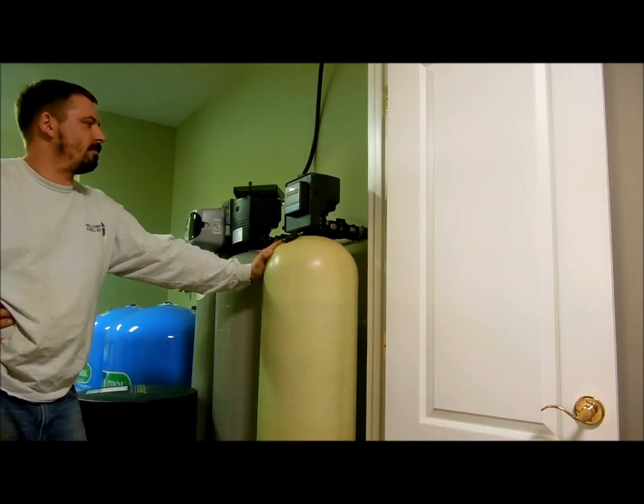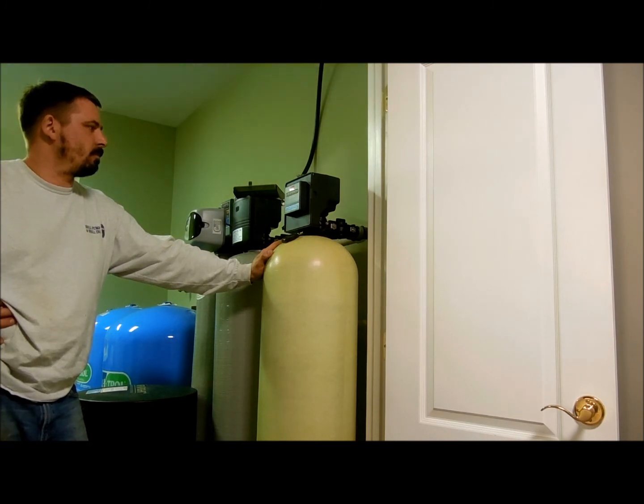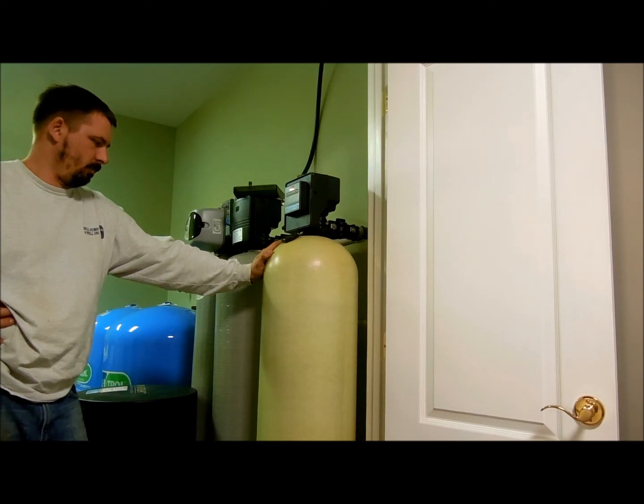Once you are done rinsing, you should make sure the clock is set for the correct time of day. Your filter should already be programmed when and what time of night to backwash. Your filter is back in service. It is nice to recheck the pH to make sure you are above a 7. This is a little tricky because you have been using the water at a high volume with no break in use for contact time. You should wait 5 or 10 minutes before you recheck the pH.